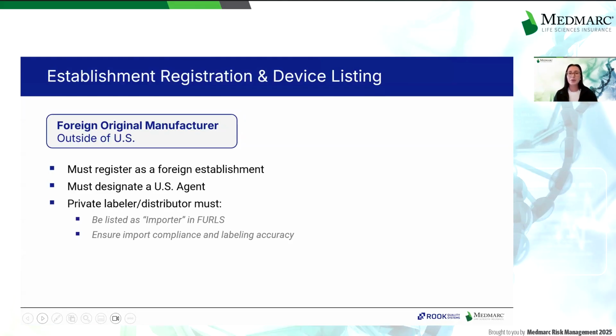For foreign OEMs, those that are outside of the US, the regulatory requirements differ slightly. The foreign establishment must register with the FDA and designate a US agent to serve as a primary contact for FDA communications. In this scenario, the private labeler or distributor based in the US must identify as the importer of record and is responsible for ensuring that the device complies with all applicable FDA importation and labeling requirements. These steps are essential to maintaining traceability, regulatory compliance, and transparency across the supply chain, particularly when labeling, importing, and distributing responsibilities are handled by separate entities.